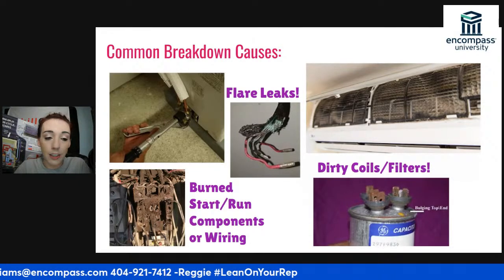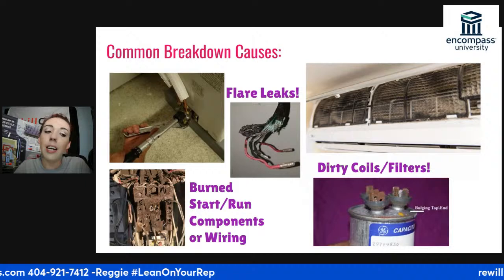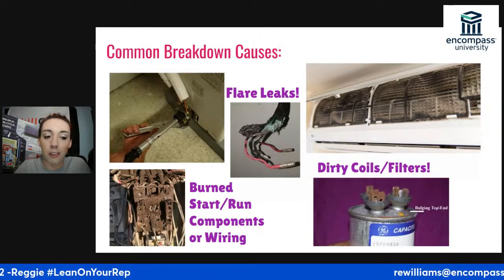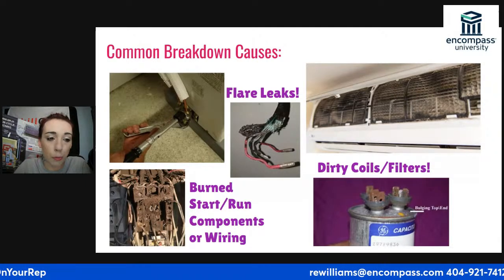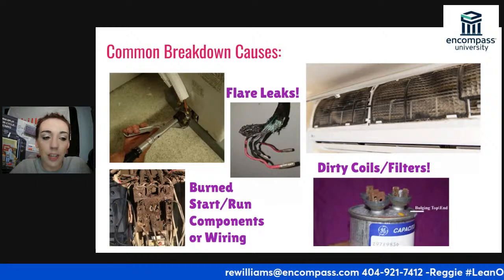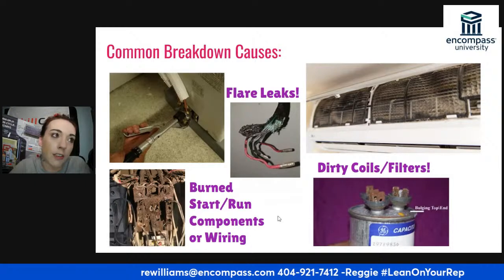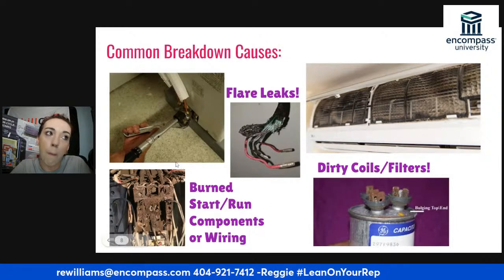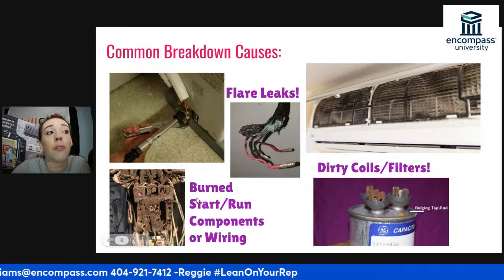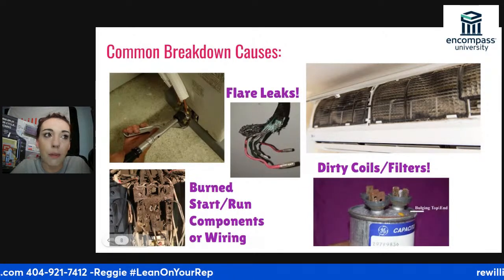Again, a contactor is not an expensive part. Typically, if it's gone bad once and you need to clean it to fix it, to get it going again, you should just be replacing it. It's not expensive, and customers typically understand what a contactor is and how important it is, because you can't get power without this. So for it to be a relatively cheap part is a pretty good thing.